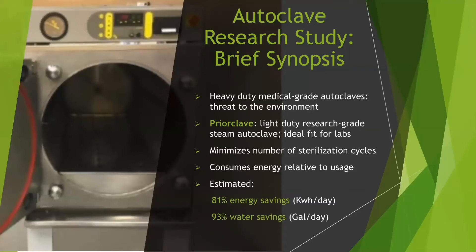In summary, heavy-duty medical-grade autoclaves in research labs maximize water and energy consumption, posing a threat to the environment. Therefore, we conducted a study proposing the Priorclave, a light-duty, research-grade steam autoclave, which is an ideal fit for research labs and educational institutions. This eco-friendly version minimizes the number of sterilization cycles, consumes energy only relative to usage, and estimates 81% energy savings in kilowatt-hours per day and 93% water savings in gallons per day. Our study aims to track the energy metrics of the conventional medical-grade autoclaves and convince laboratory personnel to switch to the newer, cost- and energy-efficient Priorclave, without interrupting ongoing scientific research.